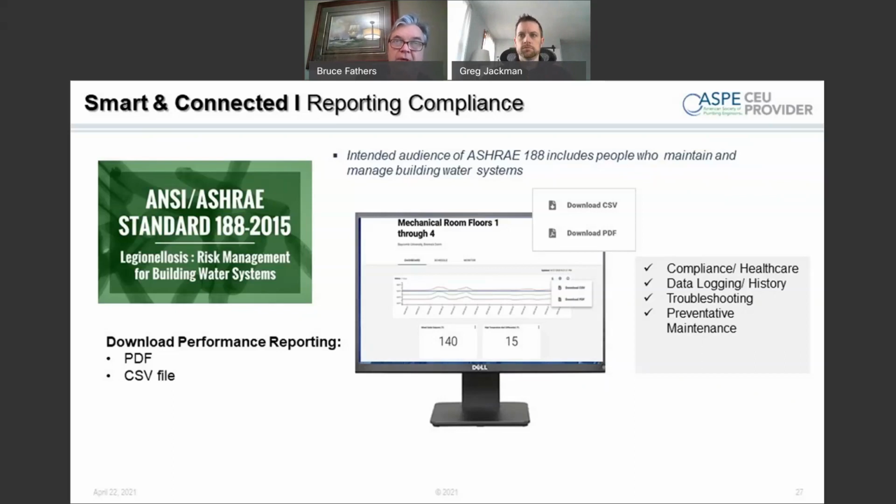But if you look at recommendations from the CDC and ASHRAE, your hot water source, I believe, is 140 and distributed at a minimum of 124. We believe personally that should be a little bit higher, right? Because Legionella is becoming a much bigger issue. But again, it's that risk balance trade-off that you've got to play with.